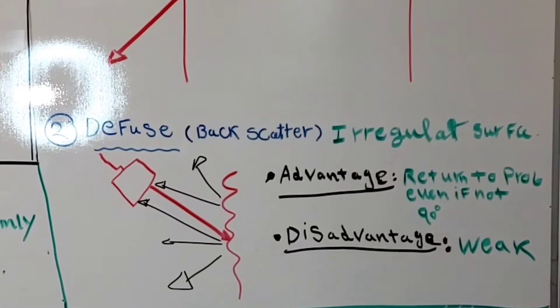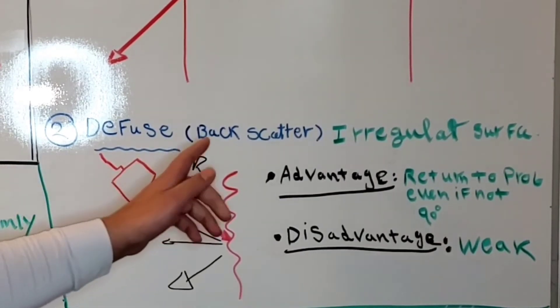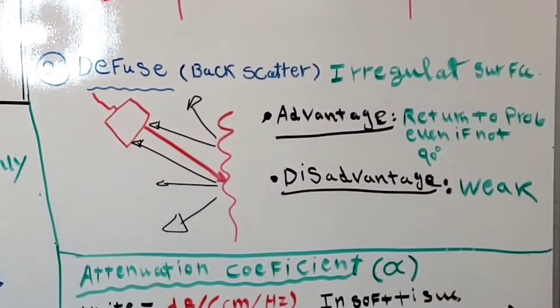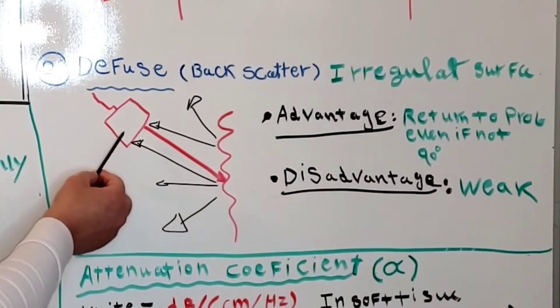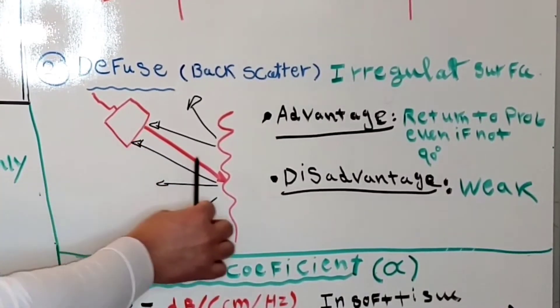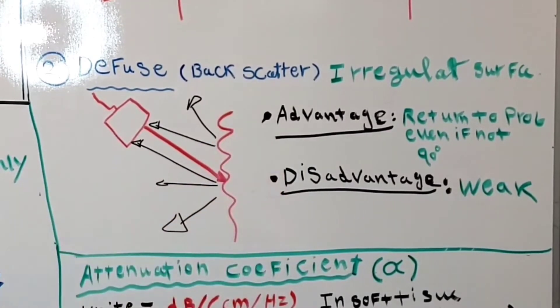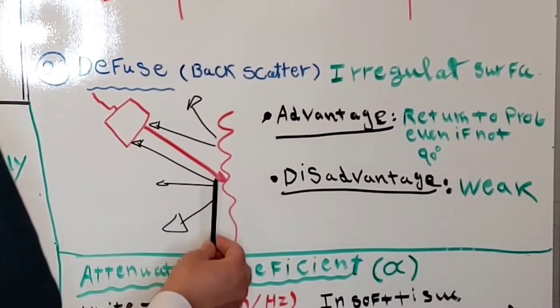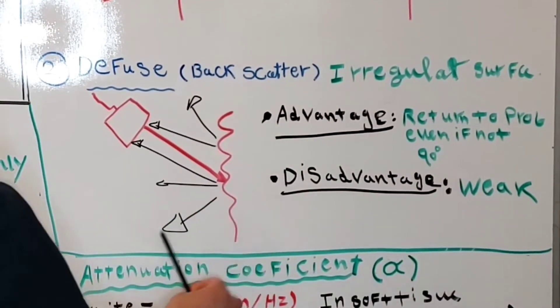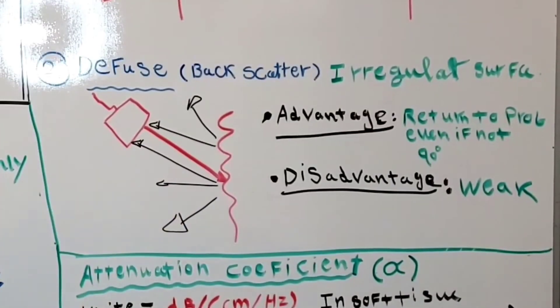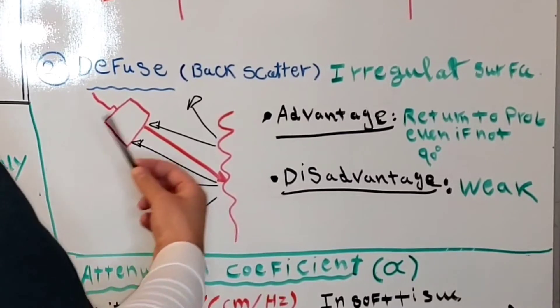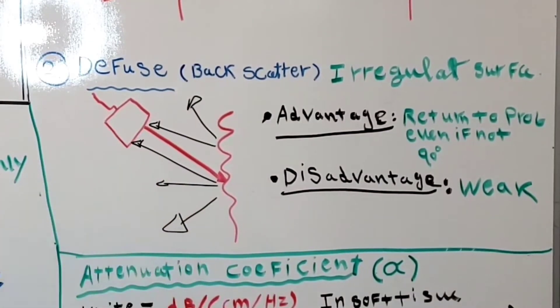The second type of reflector is the diffuse or backscatter reflector. The backscatter reflector occurs when the surface is irregular or not smooth. An advantage is that the sound beam will return to the transducer even if the transducer is not perpendicular to the reflector. The disadvantage is that the reflection is very weak, because some of the reflected energy travels away from the transducer.